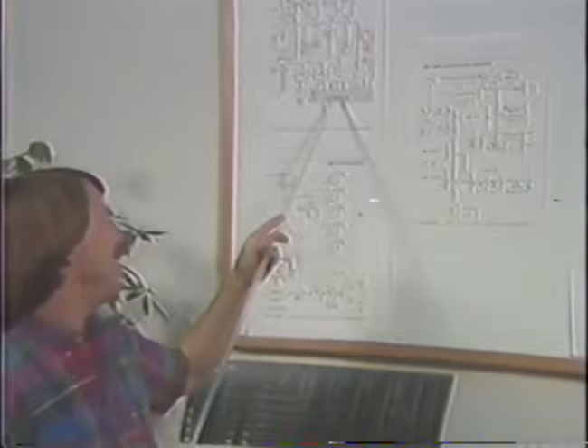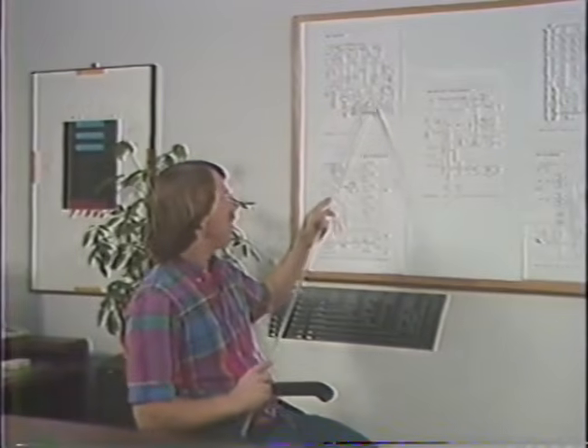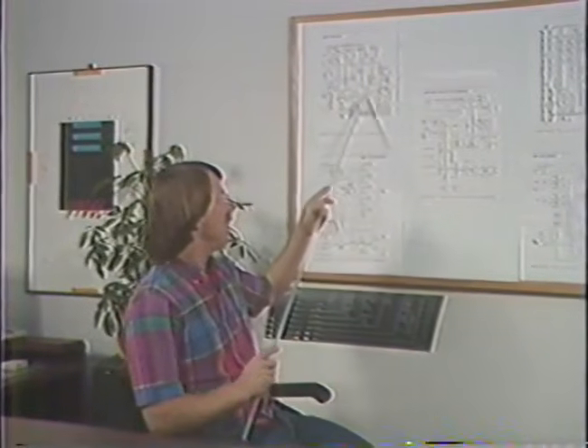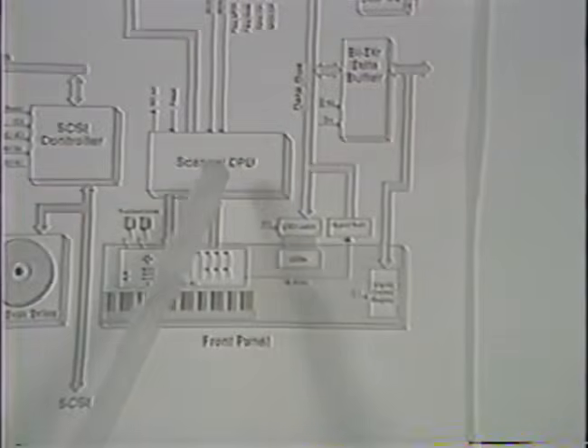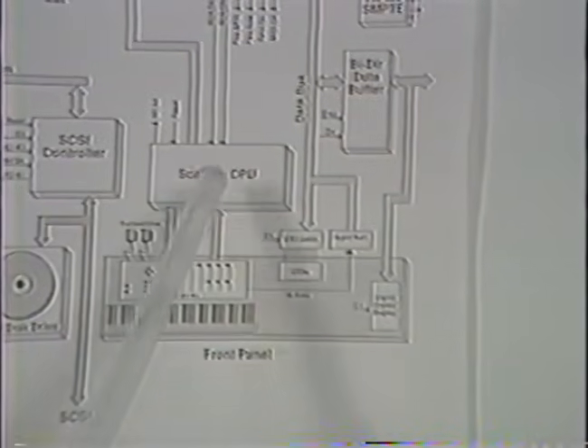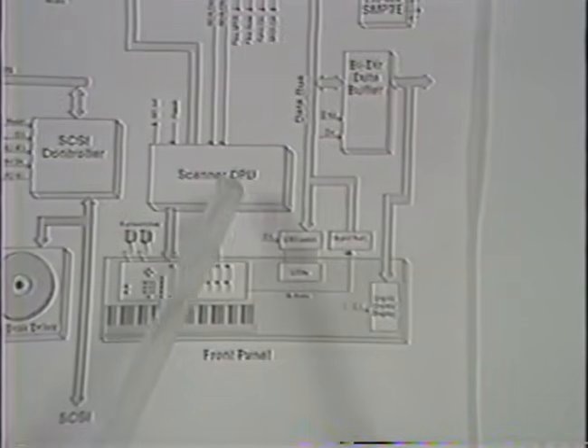Let's get down to specifics with the CPU board. If we start from where a user would typically start, pressing a button on the front panel, the first thing we run across is the scanner CPU. This is a separate little computer inside and should be pretty familiar to those of you who have worked on Emax before. It's the same chip with the same program in it, performing basically the same function. The scanner's CPU job is to inform the main CPU whenever a change has happened on the keyboard or front panel, and it does so through a parallel interface on over to the main CPU.